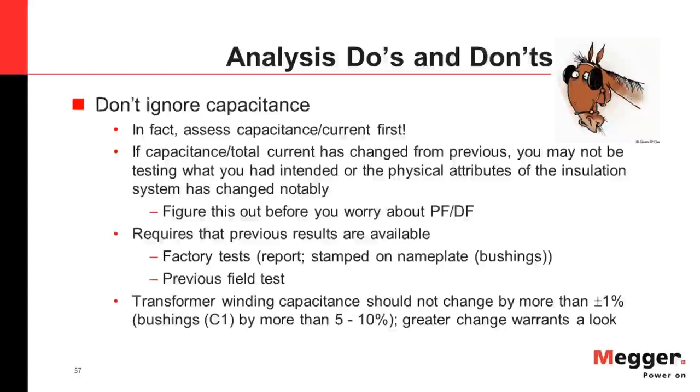Now next, don't ignore capacitance, even if you don't have a benchmark value. So what do you do in those cases? Well, in those cases, you're looking out for abnormally low current or capacitance results.